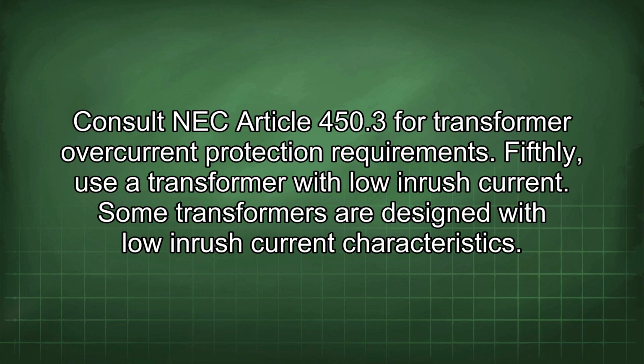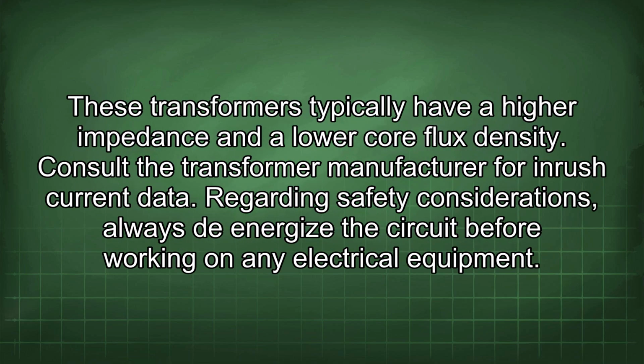Fifthly, use a transformer with low inrush current. Some transformers are designed with low inrush current characteristics. These transformers typically have a higher impedance and a lower core flux density. Consult the transformer manufacturer for inrush current data.